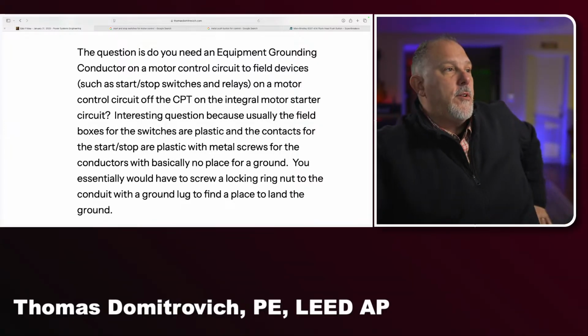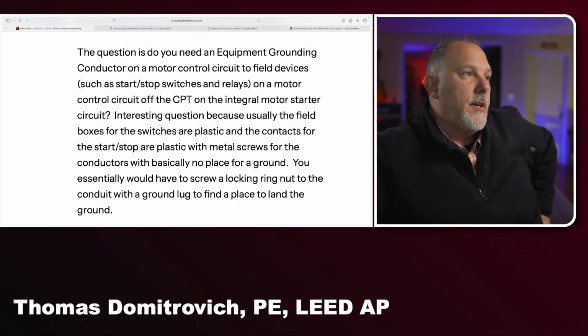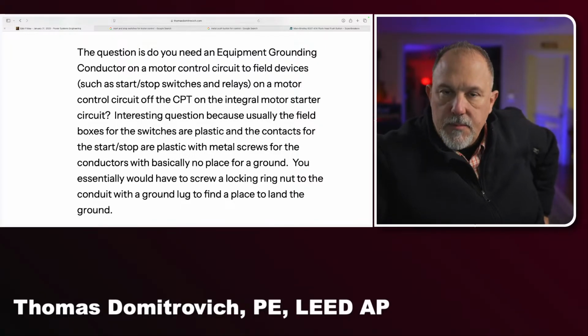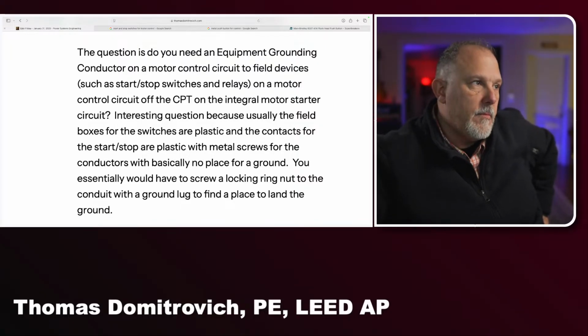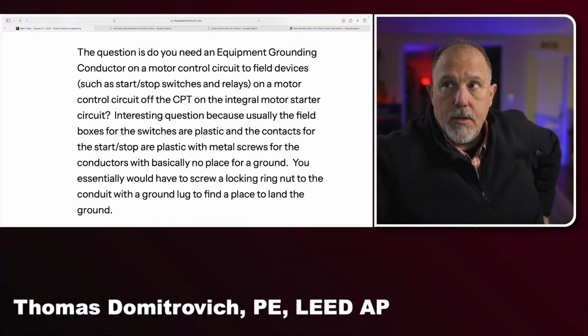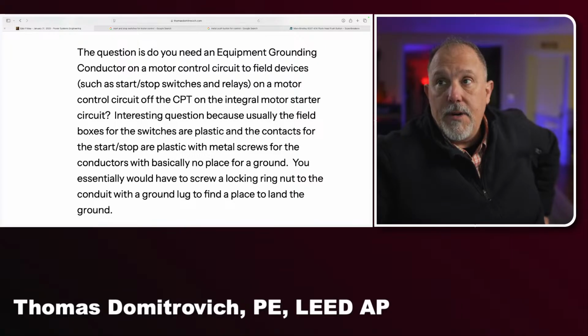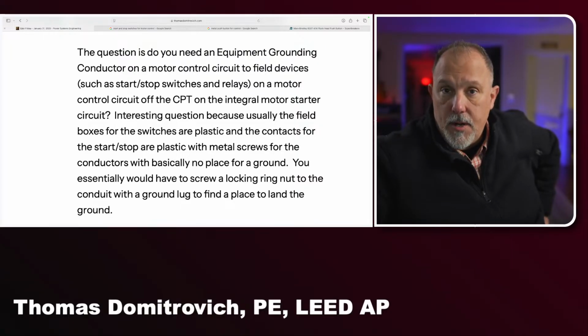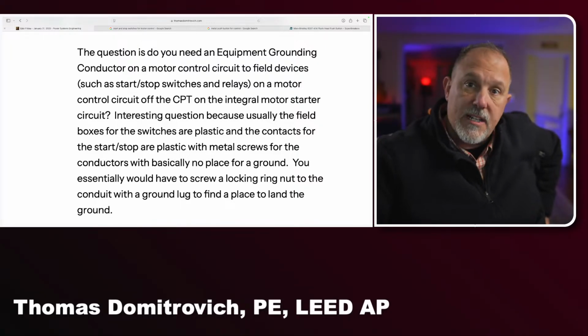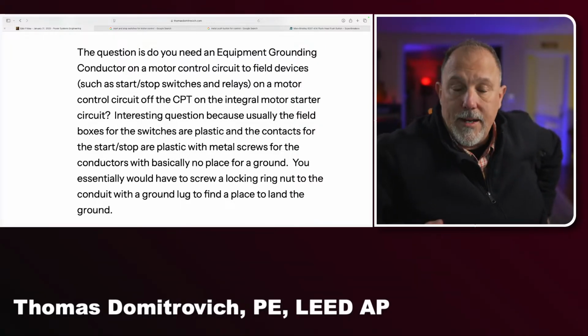I wouldn't go to Part 2. I would go to Part 5, bonding, to determine what needs to be bonded. And it's going to tell you metal parts all need to be bonded. If it's not a metal part, then you don't need to bond it. If my push start stop switch is plastic, then I don't have to bond that either. But if I apply it in a metal box, now I'm going to have to bond things together because the metal box has to be bonded, and I have to pull an equipment grounding conductor, the whole bit.